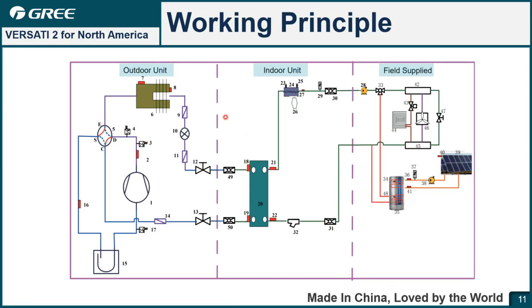Next one is the working principle for the VERSATI 2. So actually, the North America VERSATI 2 is a split type. In the package, there is one outdoor unit and one indoor unit, and some parts you need to prepare in the field, such as the water pipe and the radiator or FCU for heating. For example, we take heating as an example. Here is the compressor. In heating mode, it will discharge the hot gas. This is the temperature sensor to detect the value, and the high pressure sensor and high pressure switch to the valve, then flow to here, the filter, and this is the cutoff valve.